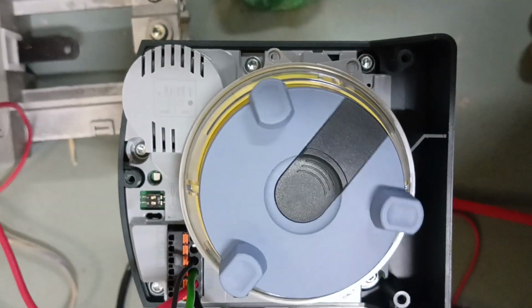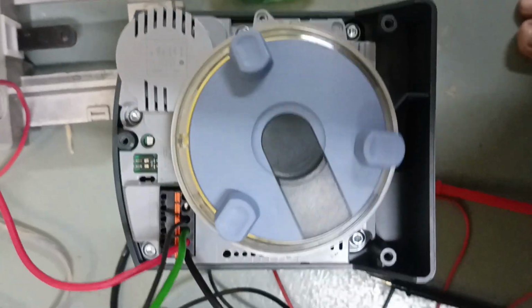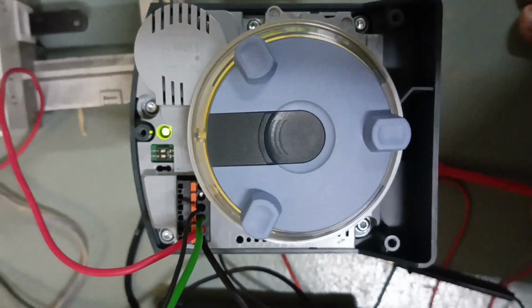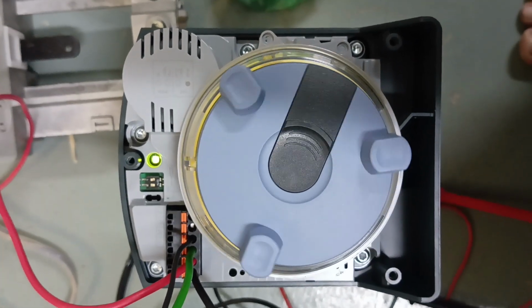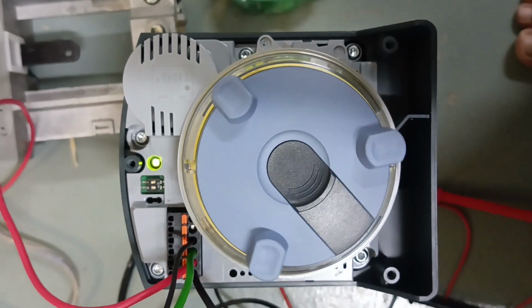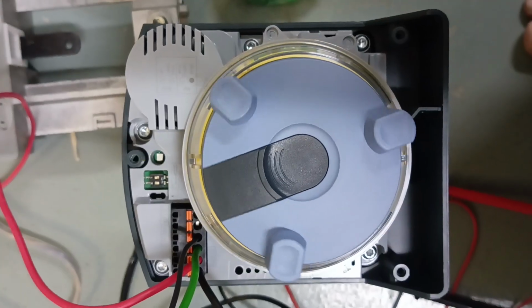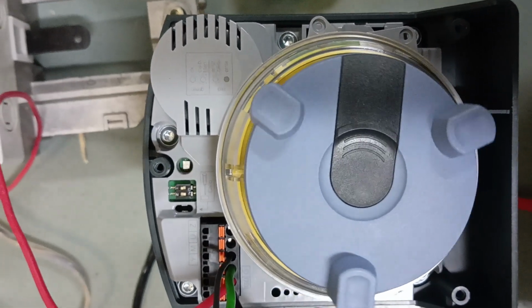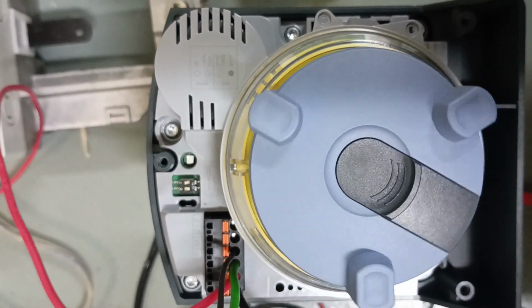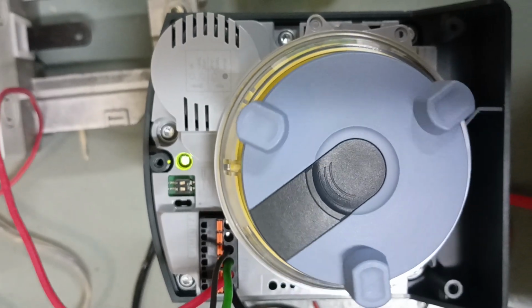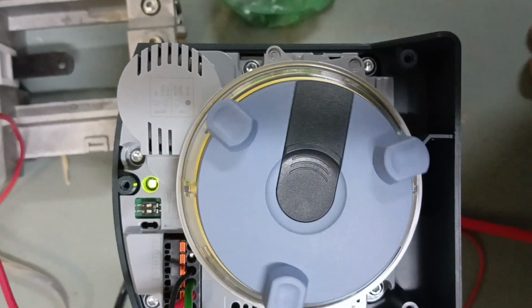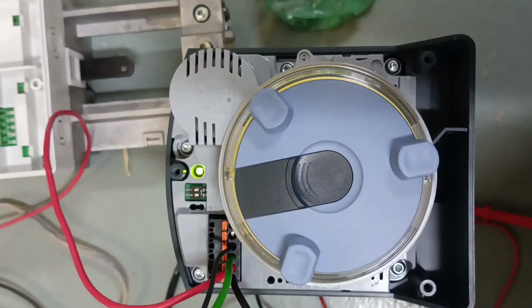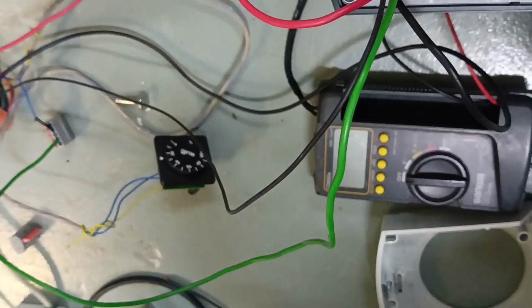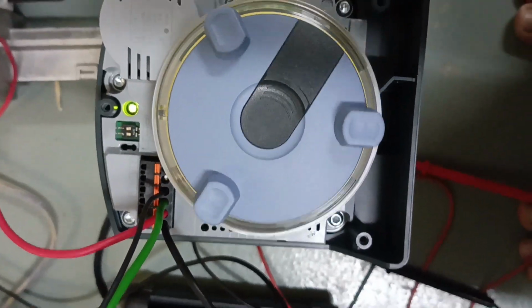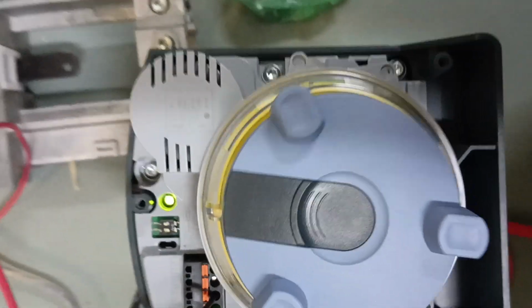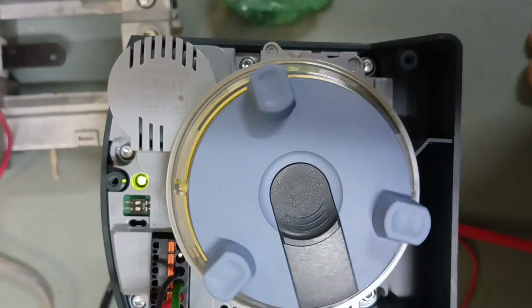So we wait until the actuator finishes. When the actuator finishes auto calibration, the LED will stop blinking. So now it's already done auto calibration. Now the actuator is moving following the 2 volt signal we gave before. This one is in linear, not exponentially increase.